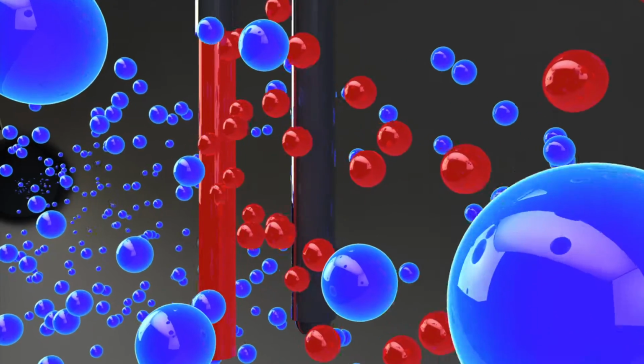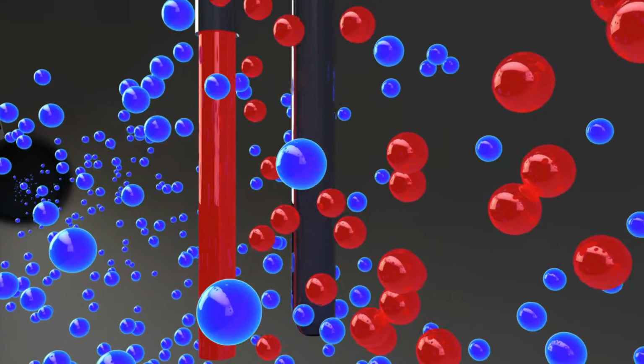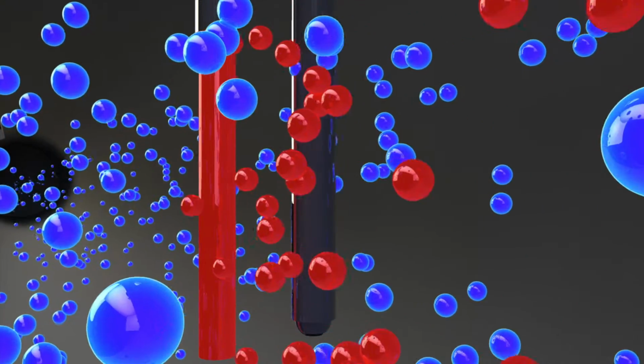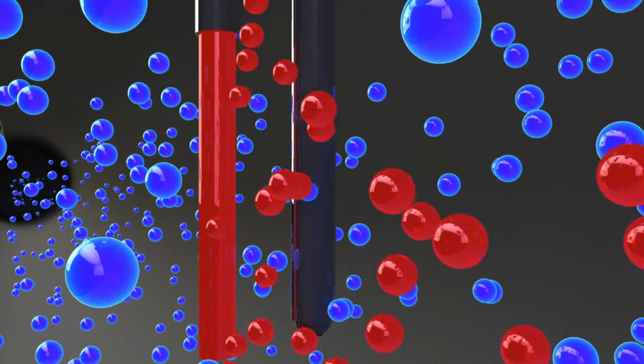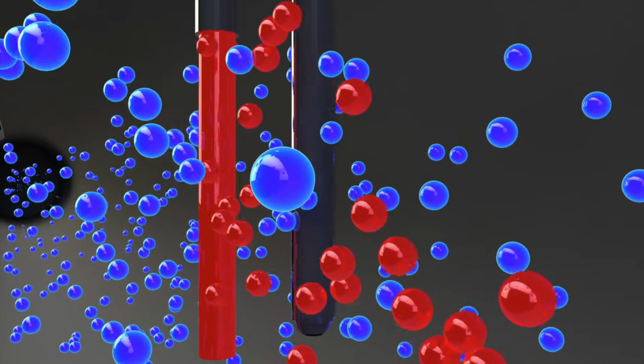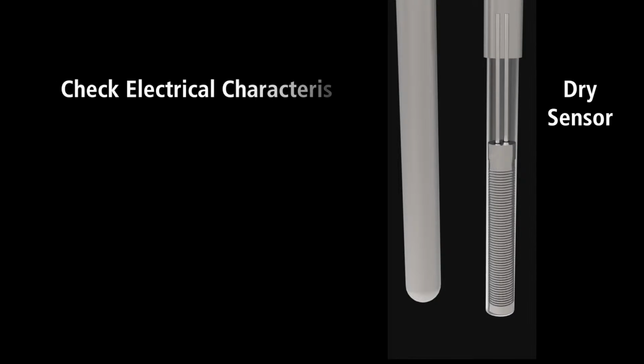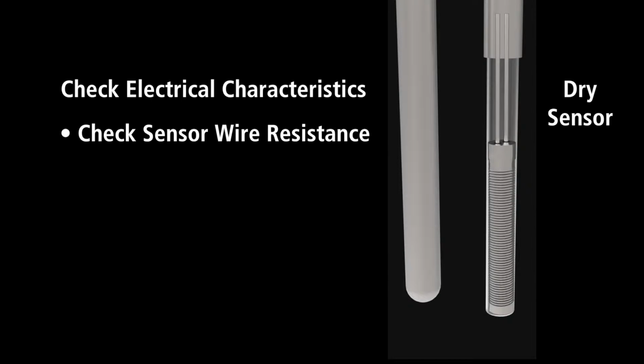All thermal meter manufacturers have generally the same method of in-situ calibration validation to confirm the original factory calibration while checking for drift and assuring accuracy. The basic process makes use of the electrical characteristics of the sensor, either by checking that the electrical resistance of the velocity sensor's platinum resistance temperature detector wire has not changed over time, or by assuring that the power sent to the velocity sensor at zero flow is the same as when it was first calibrated at the factory.